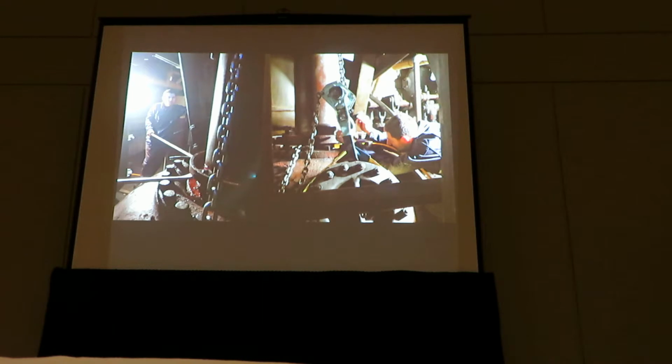There was a challenge which was more difficult than Phillipsburg. This engine had never had its water end drained properly when it was put out of service, and the plungers and pumps are of a design with internal packing glands, whereas the ones in Phillipsburg and most of the other vertical engines out there are external packing gland. They were absolutely frozen solid, and there was absolutely no moving them at all. So in order to get the engine to move, we had to completely disconnect it from these plungers, and that's what you see going on here.